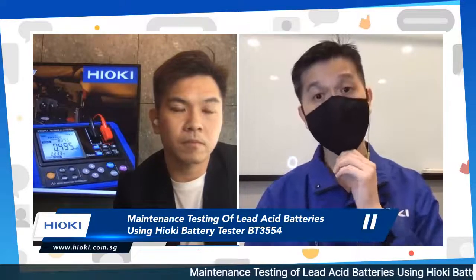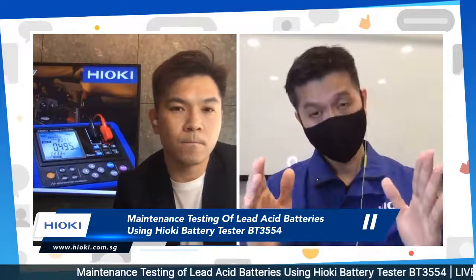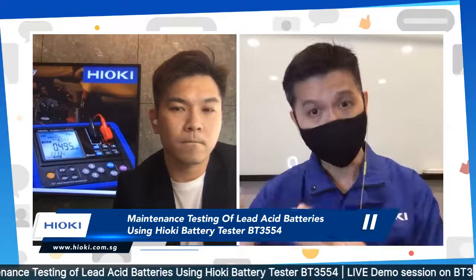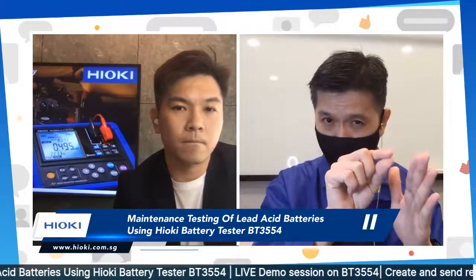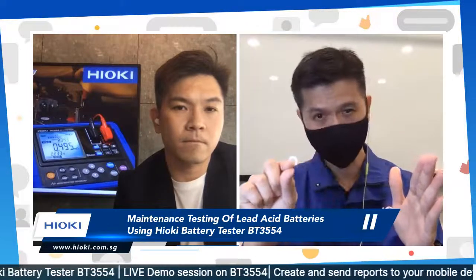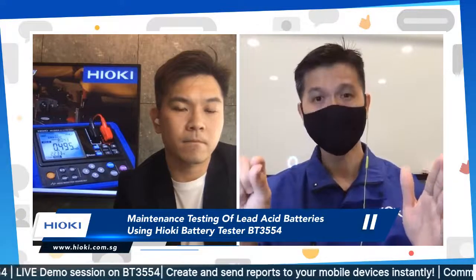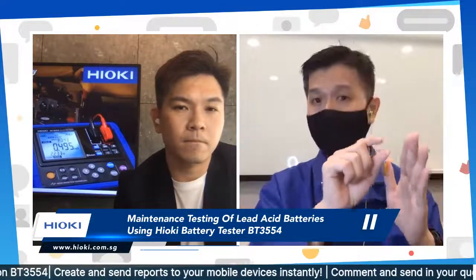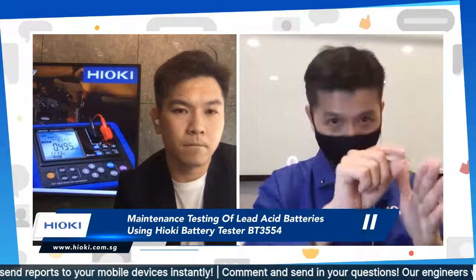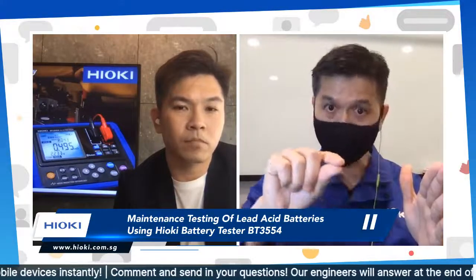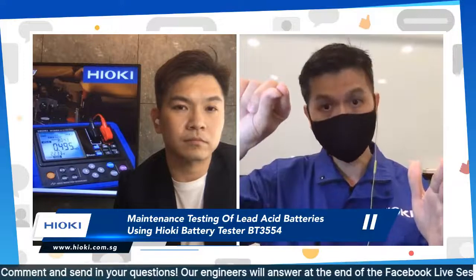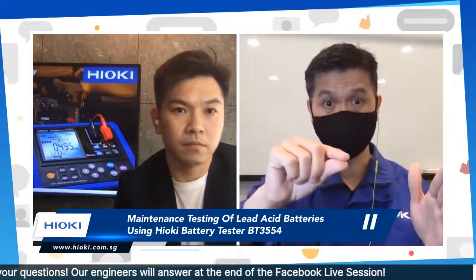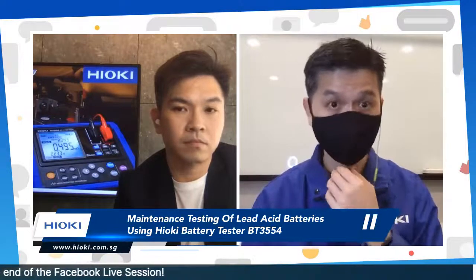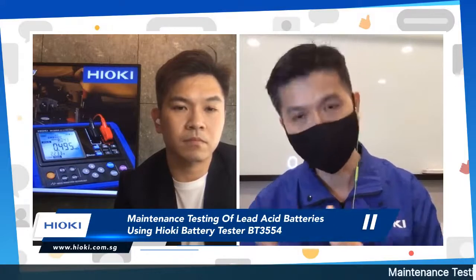Why is that so? For nickel cadmium, the degradation is very, very little over time, with very small changes. But for lead acid battery, the changes are quite significant. First year, second year, third year, then it starts to curve up, and the internal resistance starts to increase like that. So it's very easy to judge using the BT3554 for lead acid battery, but not as easy for nickel cadmium or lithium ion batteries.